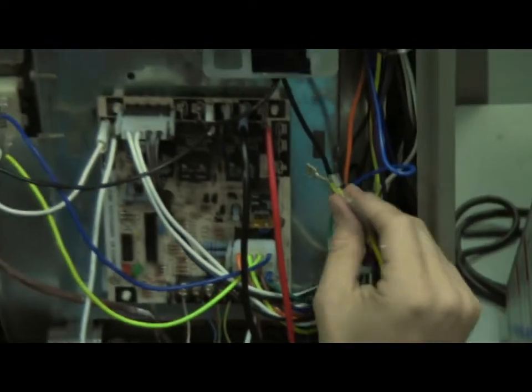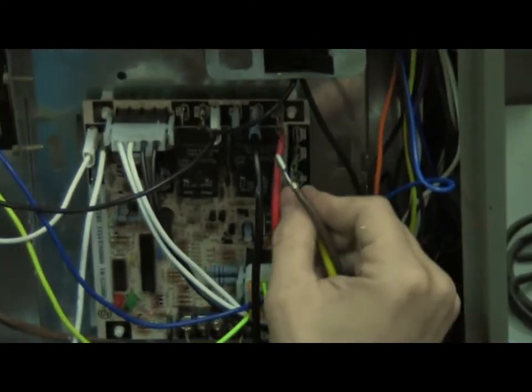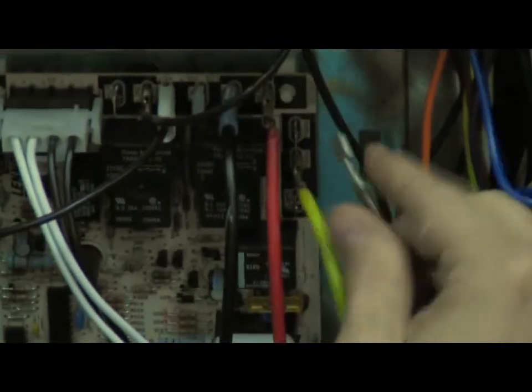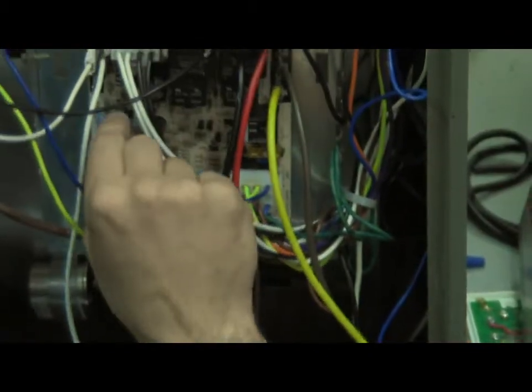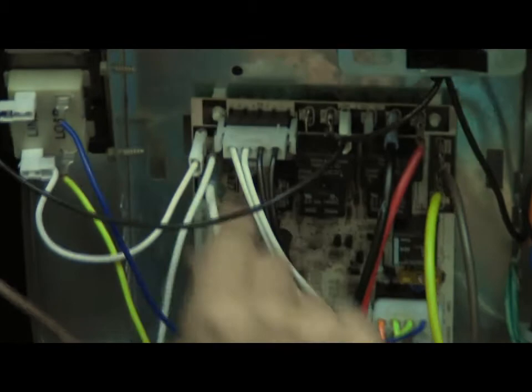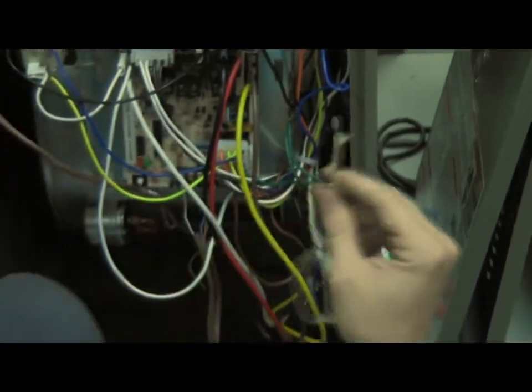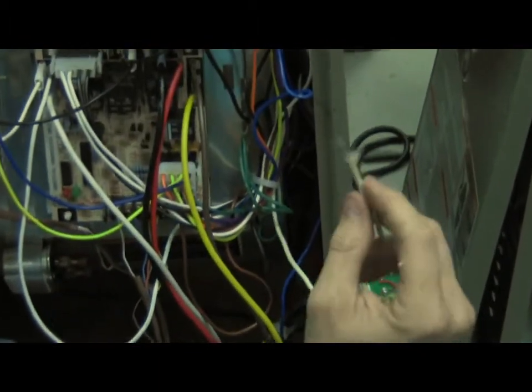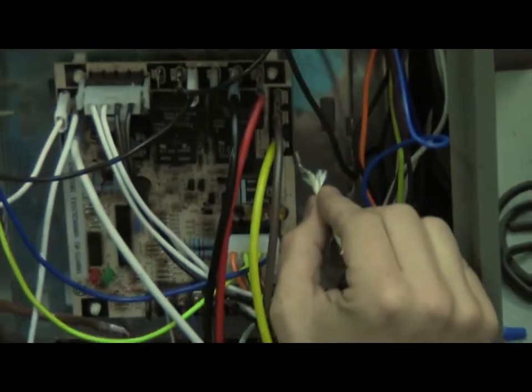The brown and the yellow are 2 other speeds that are not going to be used, and we're going to put those on the 2 terminals that say park because they're not being used. The only other one left for the blower is the neutral. It goes to one of the remaining 3 neutrals on the side of the board over here. The only wire left is the wire here that goes to the flame sensor for the heater, and it goes right here on the right hand side of the board where it says FS and flame.